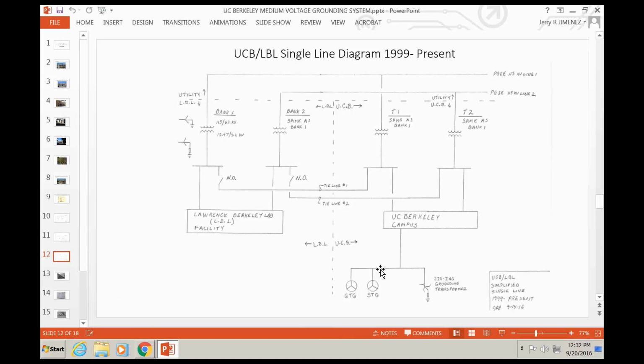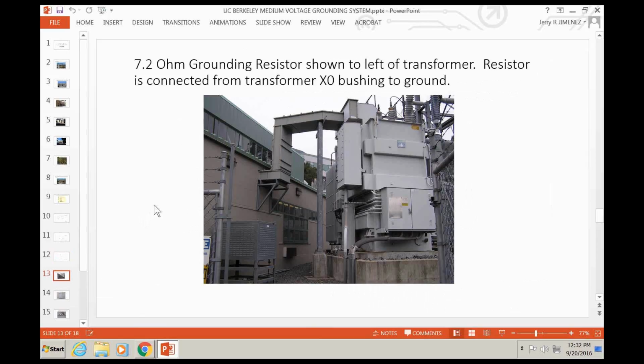So again, nothing changed here at the cogen plant: gas turbines, generator, steam turbine, and our zigzag grounding transformer. I want to take a moment here and look at the details of these grounding resistors. This is one of our big transformers at the Hill sub at 37.5 MVA. If you run the fans, you can get up quite a bit higher. The 115 kV is coming in over here. I can't see the exact connections, but this middle bushing is 115 kV. The 12 kV is coming out through this air terminal chamber, and the three phase conductors come up through this bus duct and down into the building and feed our switchgear.